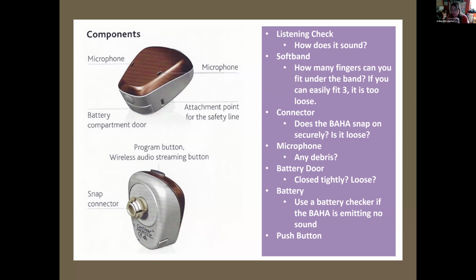Or is it falling off as you're trying to connect it? If it is, and if it's on a soft band, it could be that the piece on the soft band where you connect it needs to be replaced, or there could be something going on with that snap connector, and it needs to go in for repair. Look at the microphones. These are on the front part of the BAHA. If there's any debris, brush it off. And always check the battery door. Is it closed all the way?